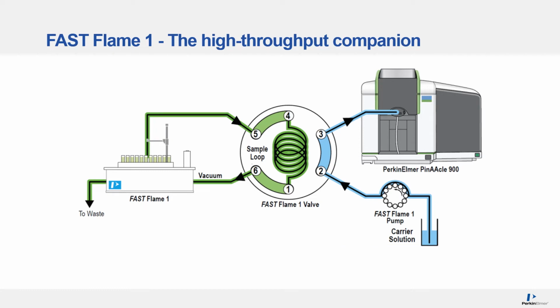For users that require high throughput and aren't as concerned about doing dilutions with their autosampler system, then we have the Fast Flame 1 solution for you. The Fast Flame 1 consists of a system of a switching valve and a single peristaltic pump, whereby a vacuum system is loading a sample loop, then switching the switching valve and using the peristaltic pump to drive a carrier solution at a known flow into the flame.